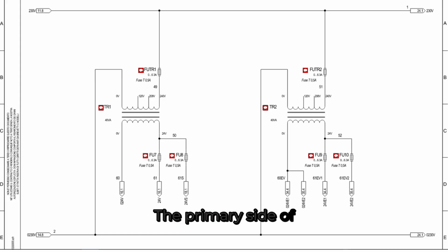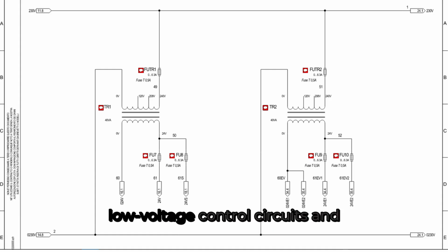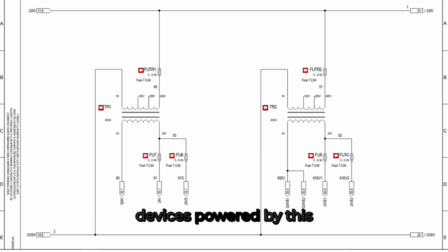The primary side of the transformer is protected by a fuse labeled FUTR1, rated at 0.5 amps, ensuring that any overcurrent or short on the transformer's primary side will safely disconnect power. On the secondary side of TR1, we can see two fuses, labeled FU7 and FU8, each rated at 0.5 amps. These fuses protect the low-voltage control circuits and devices powered by this transformer. The output from these fuses supplies 24V control power.